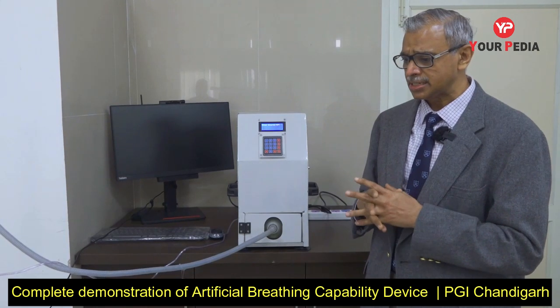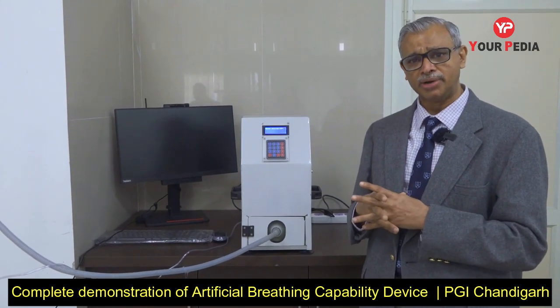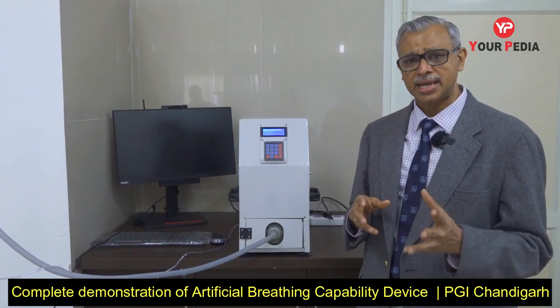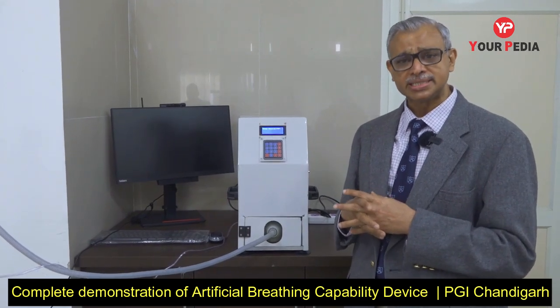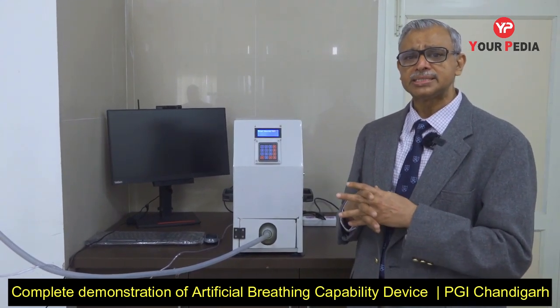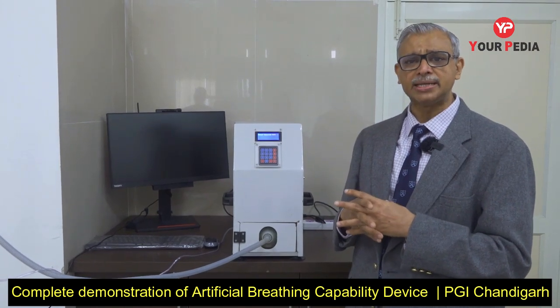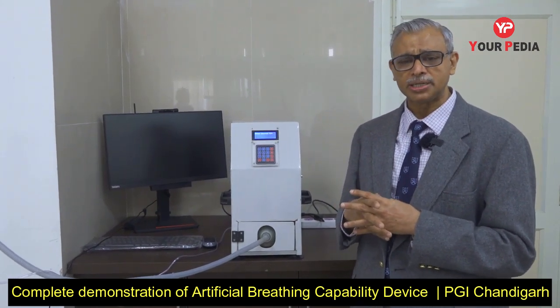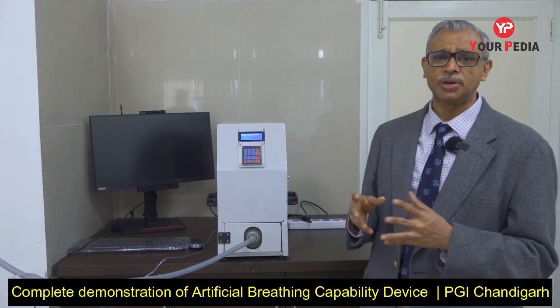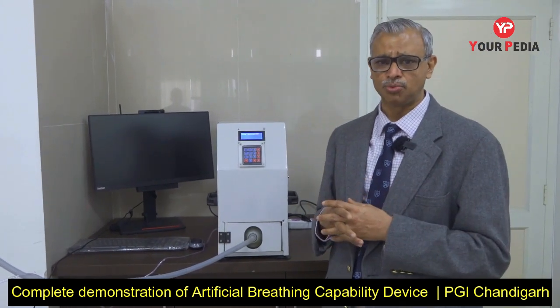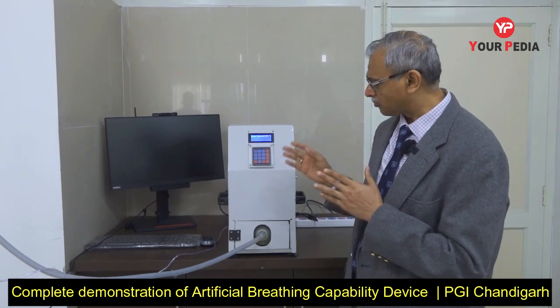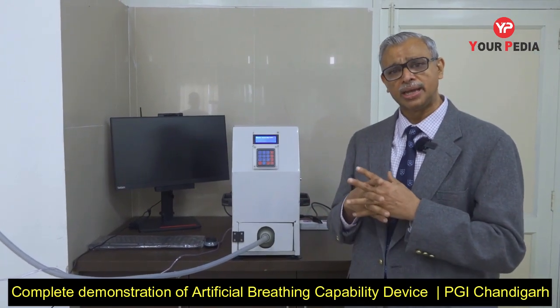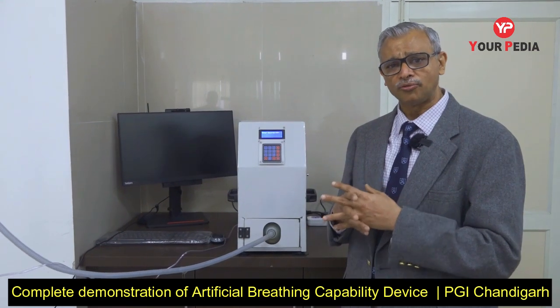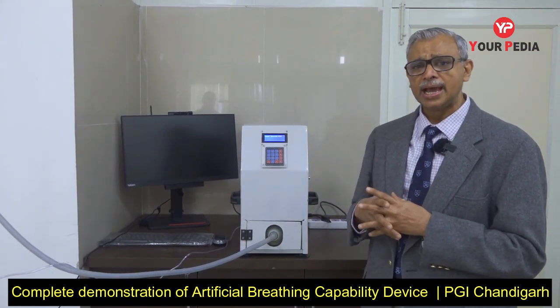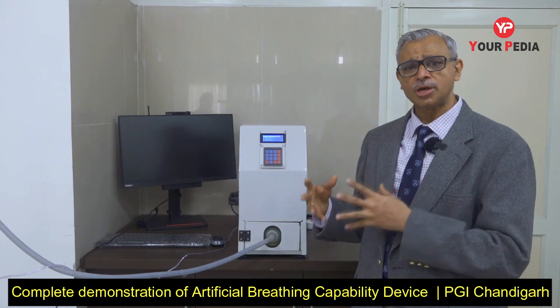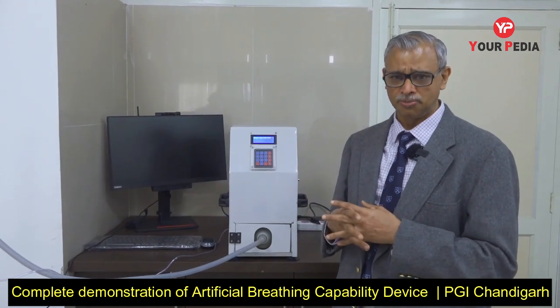A user can set peak inspiratory pressure in this device ranging from as low as 10 centimeters of water to as much as 60 centimeters of water. He can set a positive end expiratory pressure using an automated PEEP valve, which can generate a pressure from 5 up to 20 centimeters of water. This device has a flow sensor which enables us to measure flow of air or air-oxygen mixture in real time, and through a calculation of the flow also calculate the volume of air delivered to the patient.